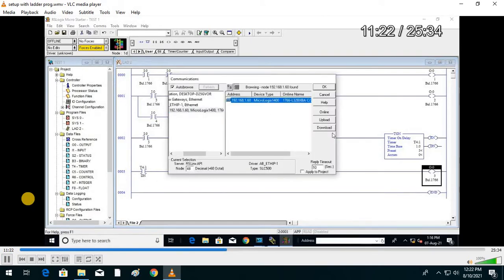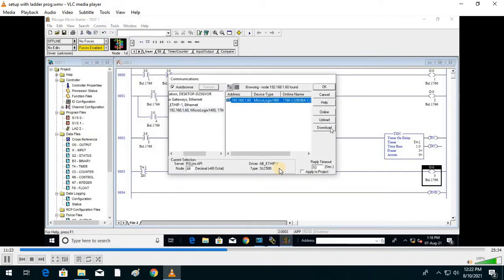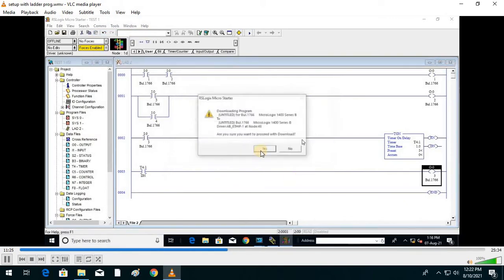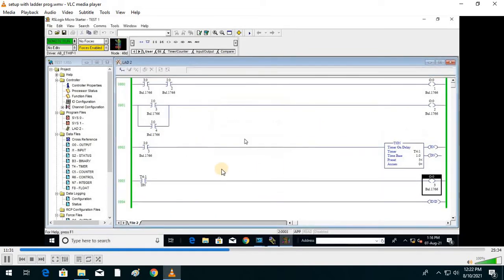Use an output and specify the output address. Go to verify project, then Comms, download the project to the PLC, go to run mode, then Online. When you press input number 5, it will turn on after 5 seconds. As soon as you press the I5 button, the enable bit is turned on but DN is not yet on because the accumulator hasn't reached 5.